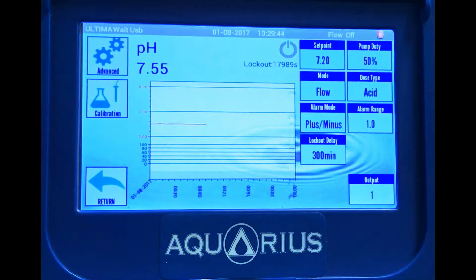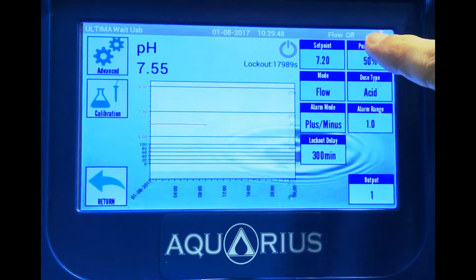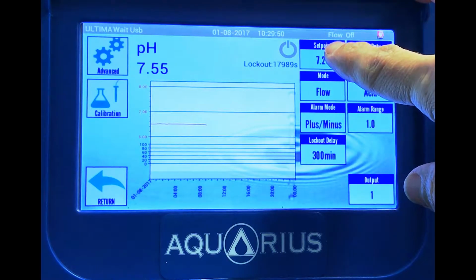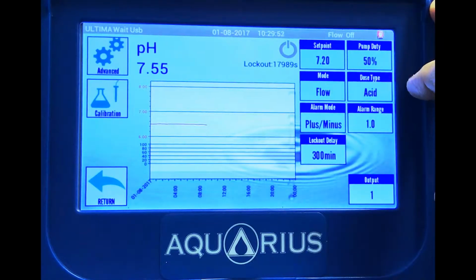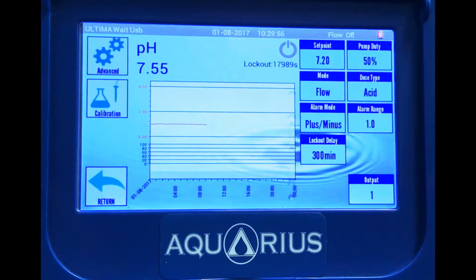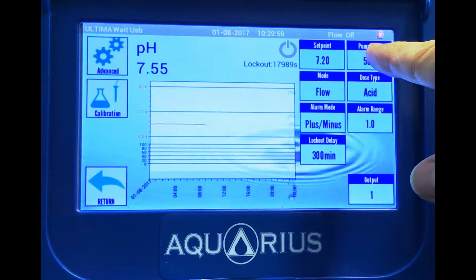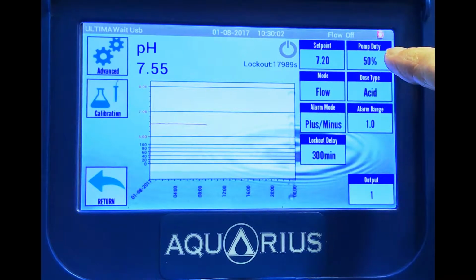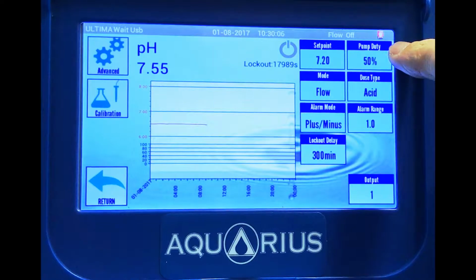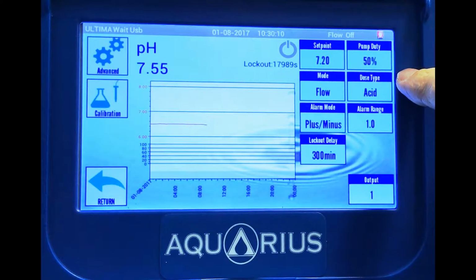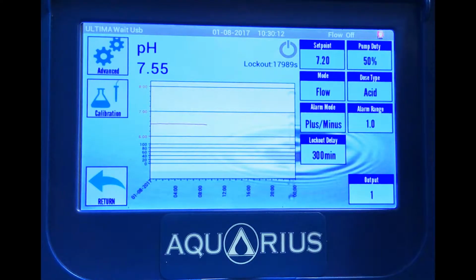So up on the right hand side here we've got all of our settings. The set point is what we want our pH to run at, 7.2. Pump duty is the percentage at which the pump will turn on for every 1 minute. At the moment it's 50%, which means the pump will be on for 30 seconds and off for 30 seconds, depending on where it is in relation to the set point.